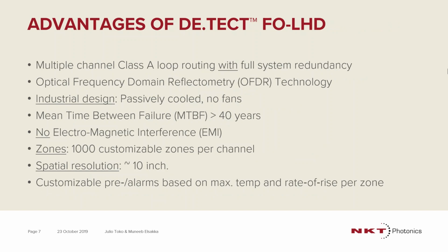Next, we'll be getting into the advantages of the NKT Detect fiber optic LHD. The multiple channel Class A loop routing provides full system redundancy to maximize coverage. We have the optical frequency domain reflectometry, which allows for a continuous laser and accuracy in the detection of the heat or fire event. Very important key point in the industrial design is to have a passively cooled controller, and there are no fans in the controller, which allows for a really high reliability, something that is common to the fiber optic sensing controllers.